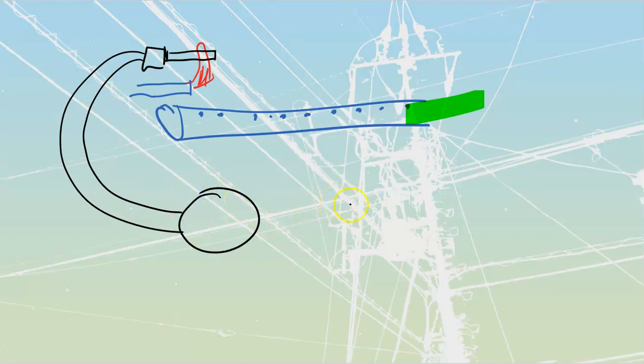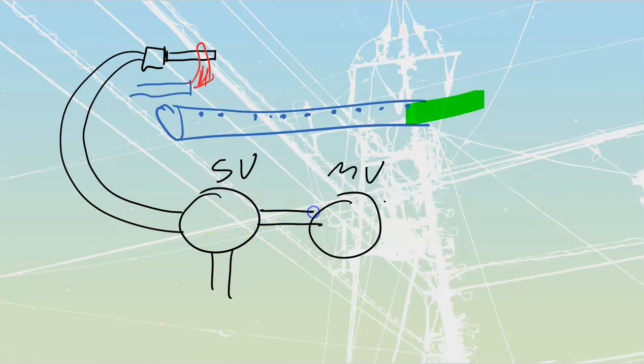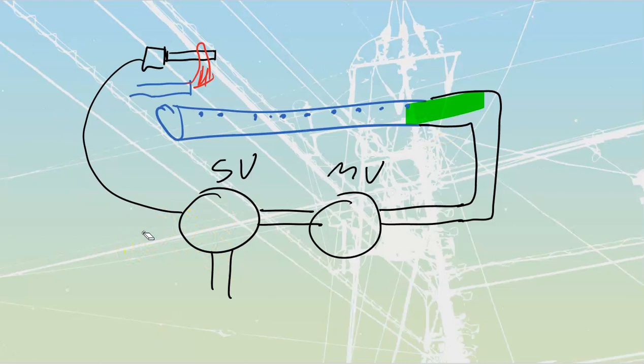I'm going to have a main gas valve, and then this is going to be the safety, this is going to be the main. We'll call that MV, we'll call that the safety valve. And so my gas comes into the system through the safety valve, goes into my main valve, which we control for our system, and then from the main valve is where it gets piped over to my actual manifold itself. Draw that so it looks like a single line.